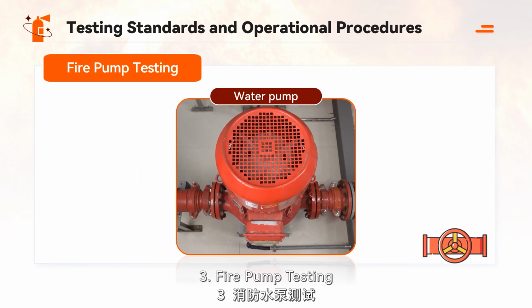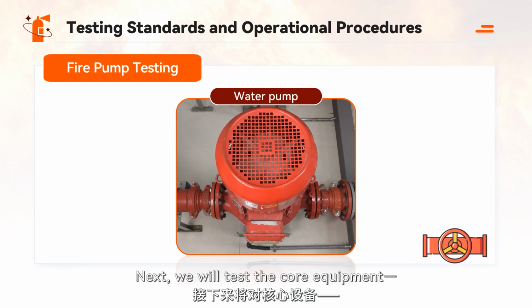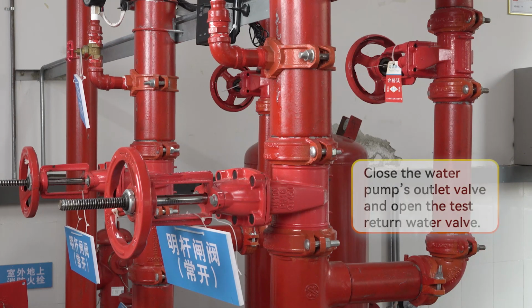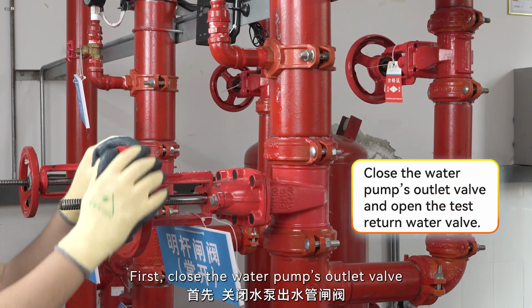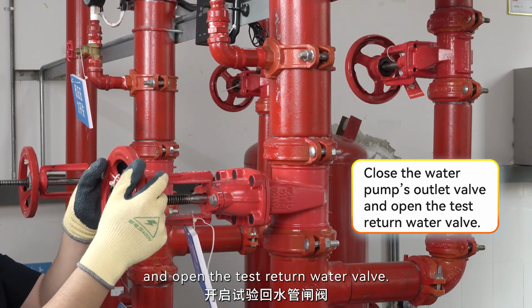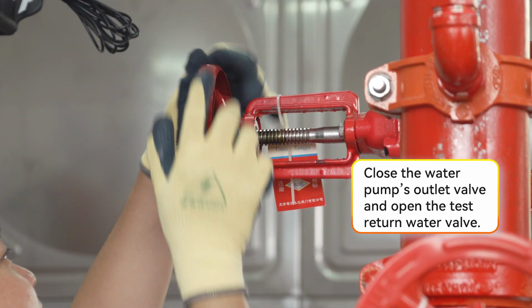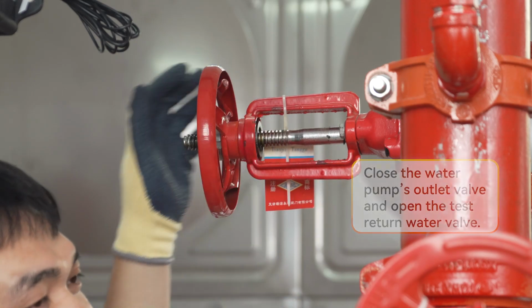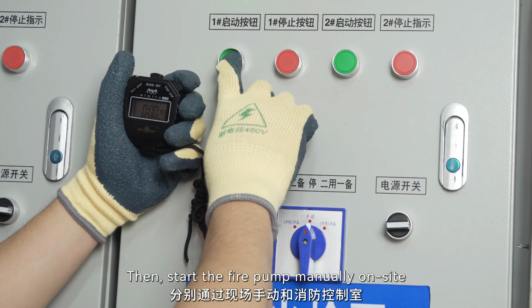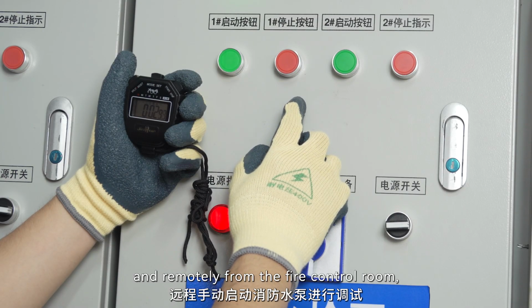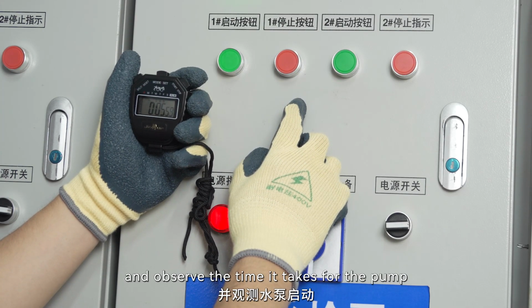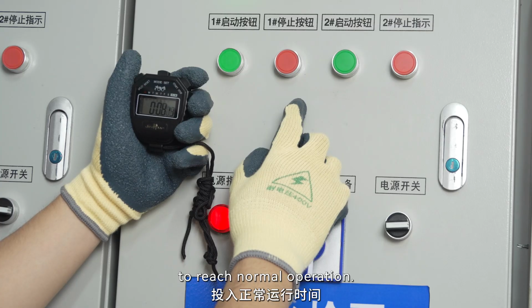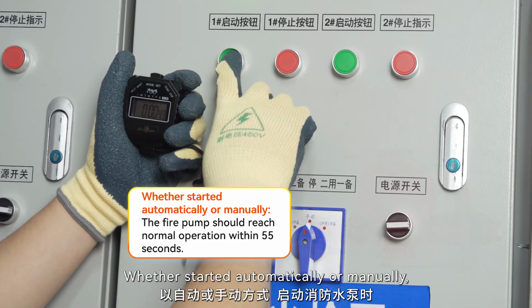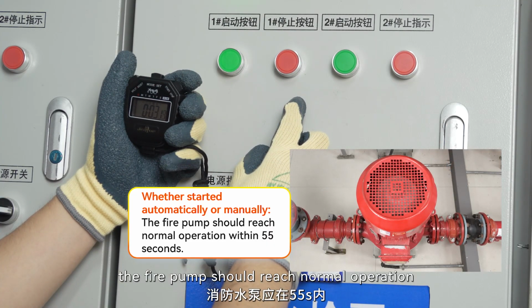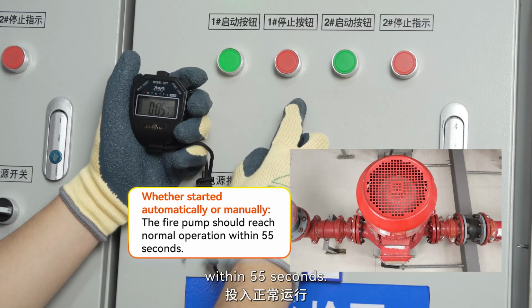3. Fire pump testing. Next, we will test the core equipment, the fire pump. First, close the water pump's outlet valve and open the test return water valve. Then, start the fire pump manually on-site and remotely from the fire control room. And observe the time it takes for the pump to reach normal operation. Whether started automatically or manually, the fire pump should reach normal operation within 55 seconds.